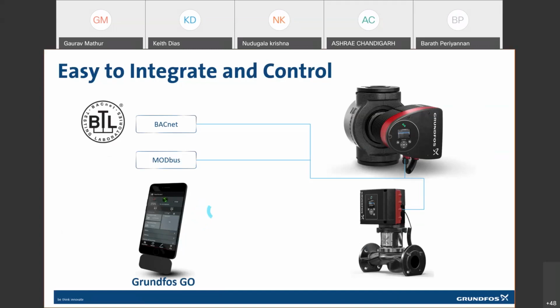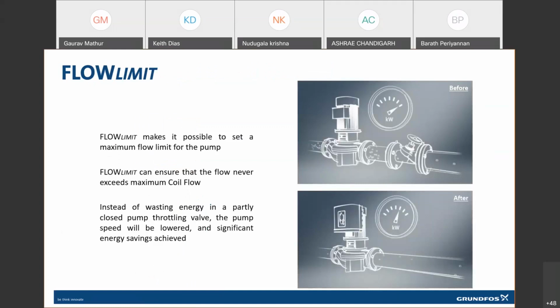So the control of these pumps can be done based on the changing outdoor conditions and on optimization algorithms, which ensure that system performance is optimized at any point of time under any load conditions. I will touch upon a few features which have made this possible. One of them is known as flow limit, where the pumps we are talking about, Magna 3 and TPE3, are able to measure the flow. As you have the flow reading available, a limit can be set on the flow, so it acts as a balancing function also, because you can ensure that for a particular equipment, the flow never increases beyond a point.